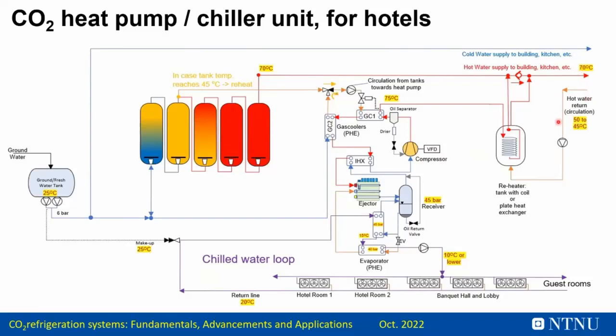And what comes back from the circulation line is reheated by the CO2, by the water which has been heated to 75 degrees, before it rejects some heat to the circulation water, and then it is stored at 70 degrees in these tanks. So the heat pump is charging these tanks, and at the same time the heat pump is producing chilled water for the air conditioning and cooling purpose in the building.